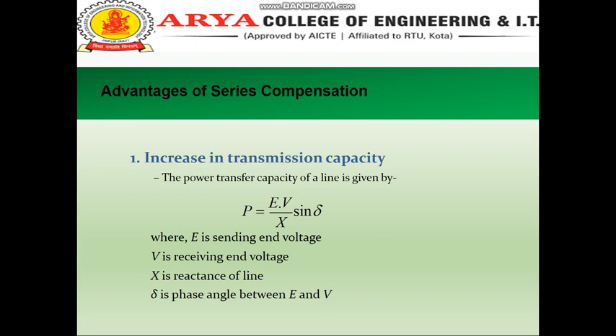Advantages of series compensation. Increase in transmission capacity. The power transfer capacity of the line is given by P equals EV upon X sin delta, where E is the sending end voltage and V is the receiving end voltage, X is the reactance of the line and delta is the phase angle between E and V. The power transfer without and with compensation can be given as P1 equals EV upon XL sin delta and P2 equals EV upon (XL minus XC) sin delta.